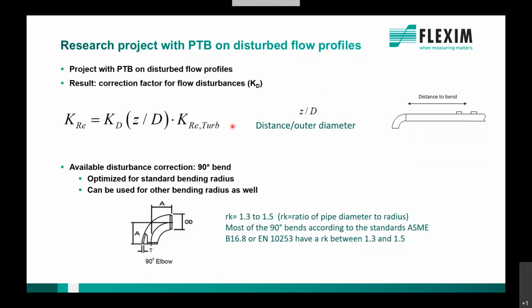What's new in that case is that we developed that in a way that this KD only depends on the distance to the disturbance and is independent of the Reynolds number. That means it works for any pipe size and any flow velocity, as long as we are in the turbulent regime. What do we do as a user? We make the installation on the pipe with the best installation spot we can find.